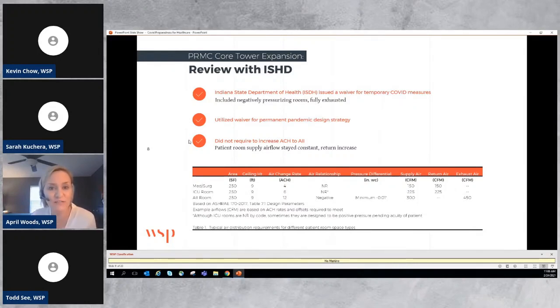One thing that really worked in our advantage is that the Department of Health was not requiring us to increase the air change rate to airborne isolation rooms, which would have been pretty dramatic. We would have been going from 4 air changes to 12 air changes of exhaust. And so with that, we were able to keep the patient room supply airflow at just above the 4 air changes. We had it designed at about 5, and then we were able to increase the return, which then became our exhaust path.